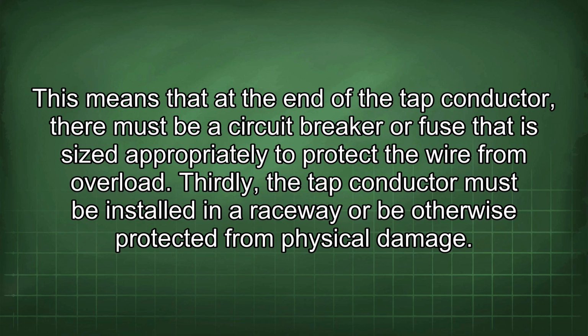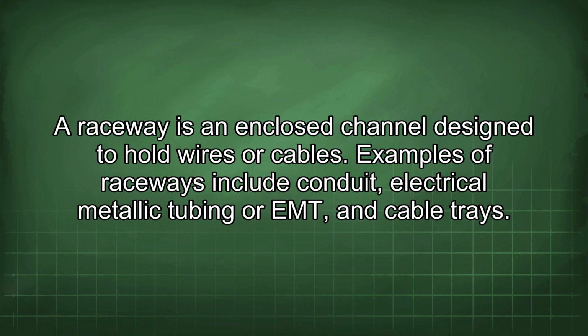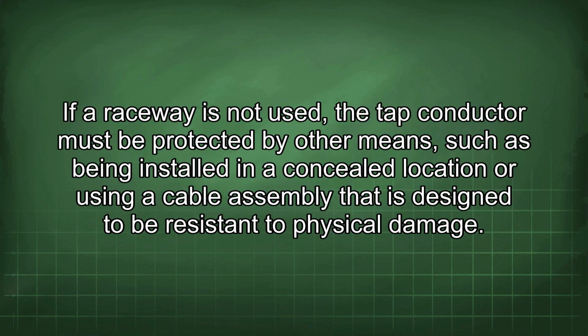Thirdly, the tap conductor must be installed in a raceway or be otherwise protected from physical damage. A raceway is an enclosed channel designed to hold wires or cables. Examples of raceways include conduit, electrical metallic tubing or EMT, and cable trays. If a raceway is not used, a tap conductor must be protected by other means, such as being installed in a concealed location or using a cable assembly that is designed to be resistant to physical damage.